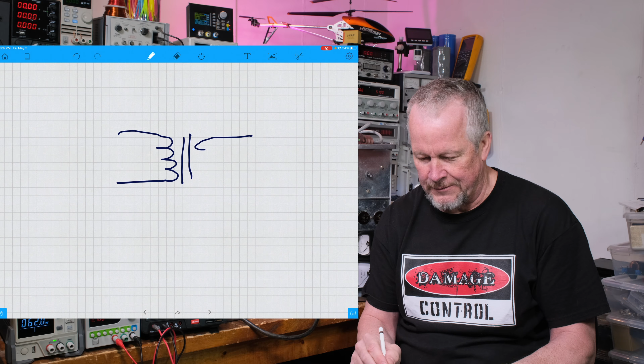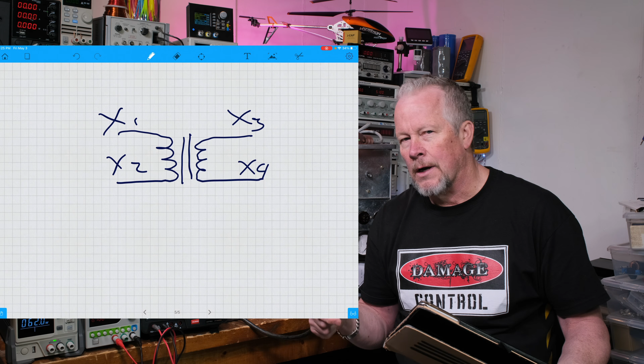It's an isolation transformer, it's galvanic isolation. Why? Because you can put an ohm meter on one of those windings, call it X1, X2, and then call the other one X3, X4. So I put an ohm meter on X1, X2, and the other lead on X3, X4, and I don't read anything, high ohms. That's isolation—it's isolated from the secondary side.